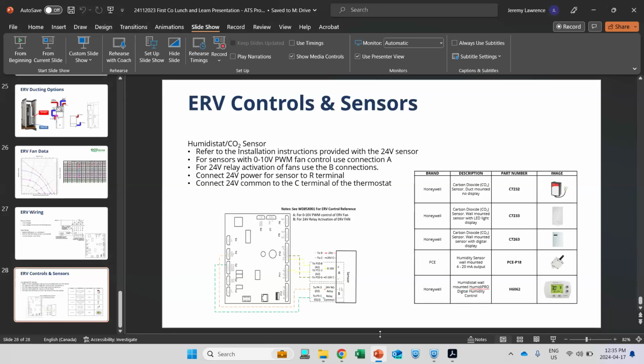Oh, yeah, what they're kind of referring to there is in standard ERVs that are standalone systems. There was a comment that there is a minimum requirement to keep fresh air and exhaust from these ventilation systems apart, but a manufacturer can have their system approved as a concentric system. So it's one vent that is able to separate the airflow enough that there's no recirculation, and they can be approved to sidestep that 10-foot minimum distance between them. So that's essentially what they've done here with the sleeve, is had the sleeve approved as a concentric vent.